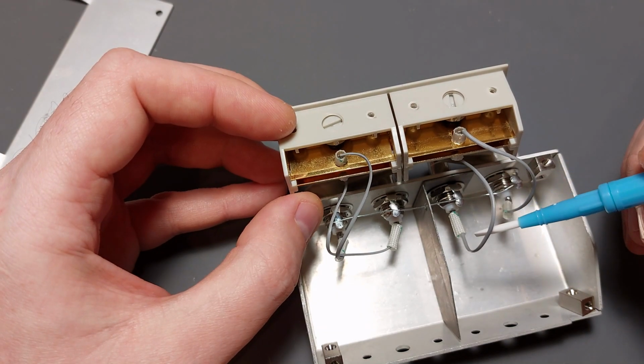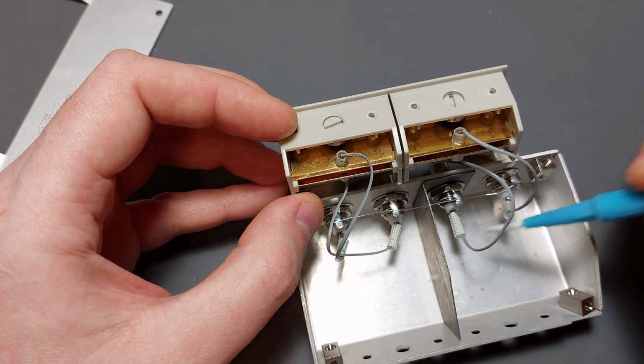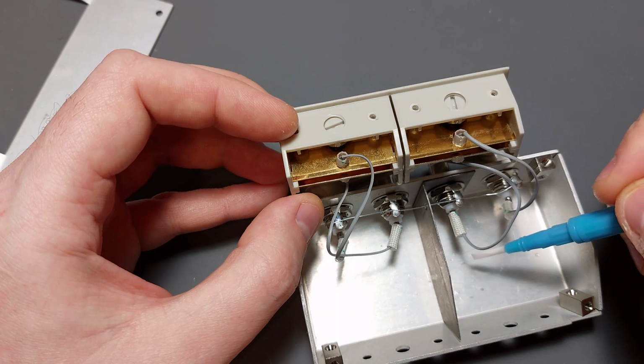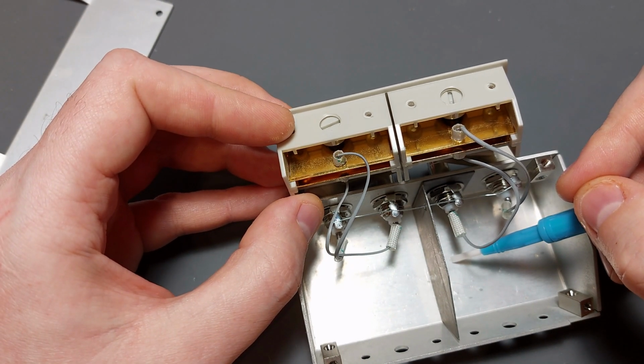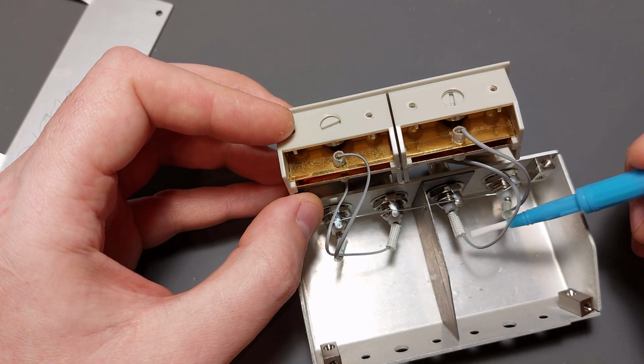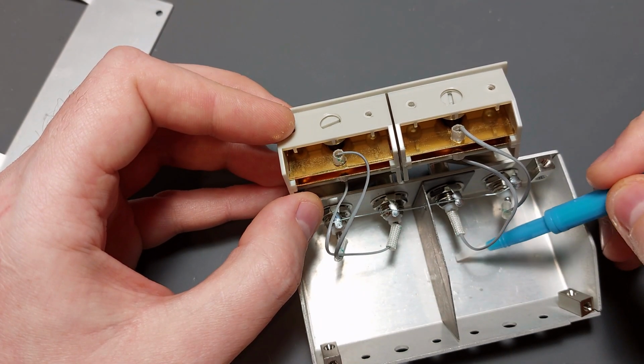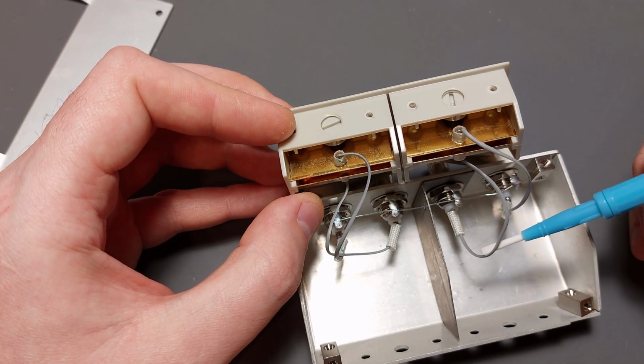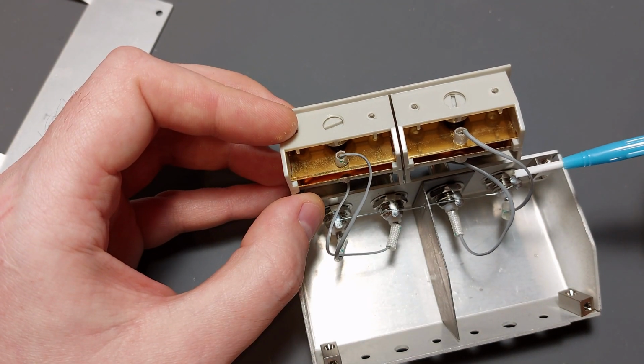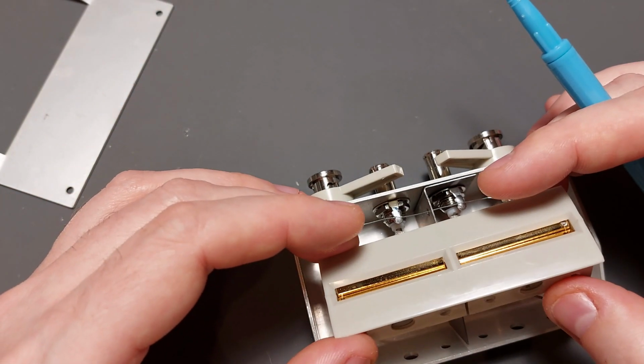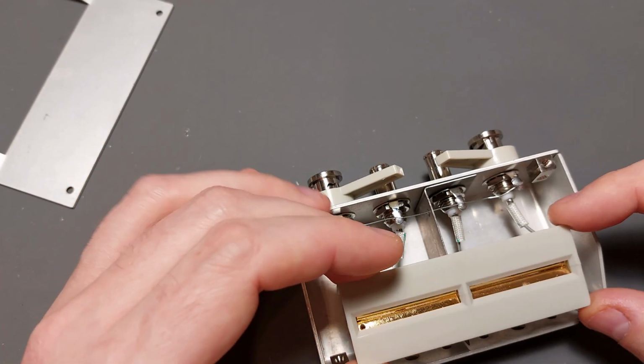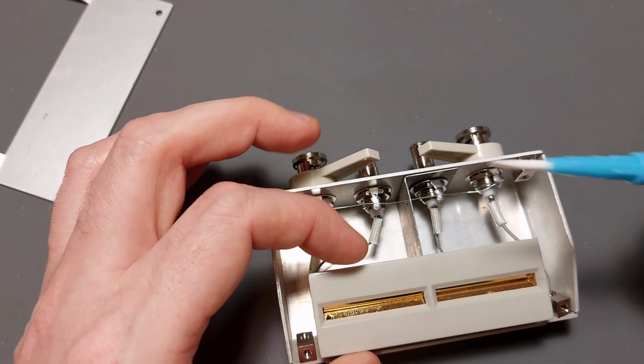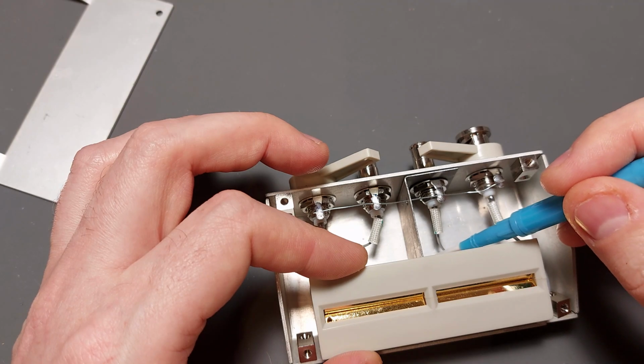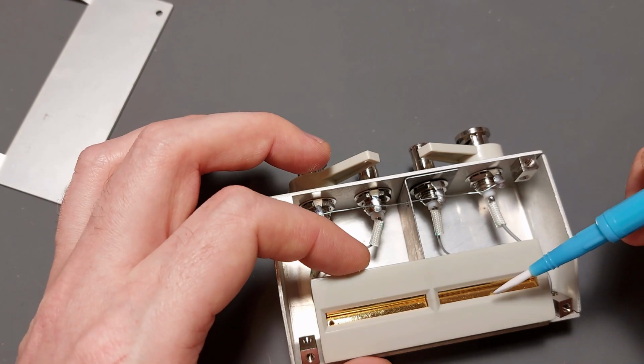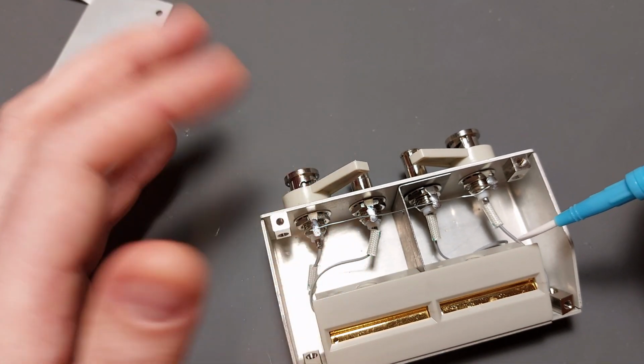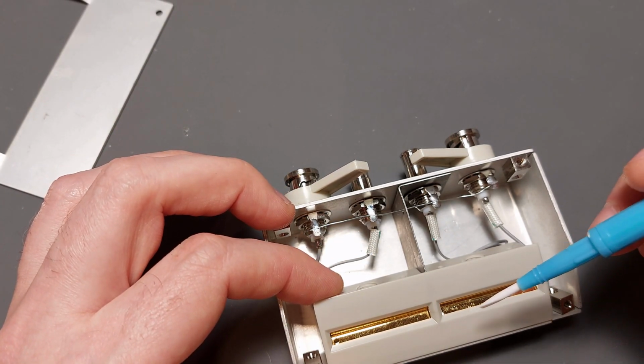Another thing these wires will bring is leakage, the current leakage between each of them, or between the wire and the shield, because the LCR meter is actually quite sensitive to current. It can measure microamps. It needs to have low leakage currents to precisely measure capacitor leakages and other stuff. So this wire can also cause high leakage. And the third thing is they are quite soft, and they can change position inside this chassis from any physical influence, like vibration or just tilting this fixture, and this will change the capacitance of the fixture. If you calibrate your fixture for short and open, and then the position changes, your calibration will go off, and this will prevent you from measuring really low values of capacitance.